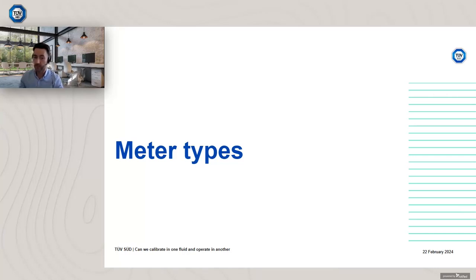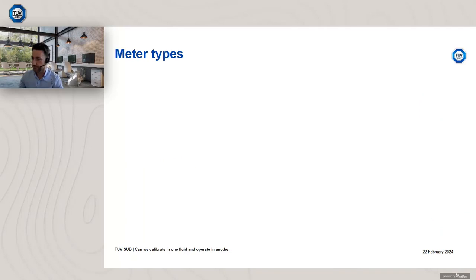However, if we take it back, one of the first questions I will ask is, what is the meter type? What are you referring to? Because not all meters are applicable. So for example, we have turbine meters. Now, turbine meters for gas are different from turbine meters for liquids. And this is known to a lot of folk, but not everyone's aware of this. So for example, if you have a turbine meter for gas use, you can't send it for calibration in water. It seems obvious, but it's something that we have to be aware of.